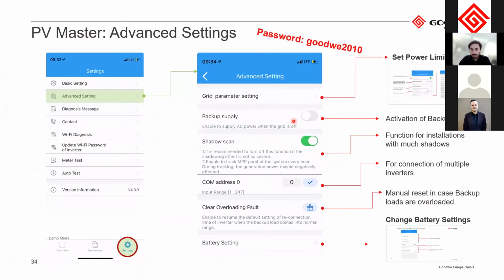The second one here is the backup supply. Activate this if you want to have the backup function activated. So as I showed you, there are 2 AC outputs. If you connect something to the backup output, then you can activate it here. The shadow scan function is only supposed to be used in case you have a lot of shadows on your PV modules. Then this one sort of triggers the inverters to check for the maximum power point more often. But in case you don't have any shadows, then it's not recommended to use this, because the inverter will not generate any energy when it checks for this power point. So it only optimizes the yield when you have a lot of shadows. Otherwise, it's more optimal to not use this function.